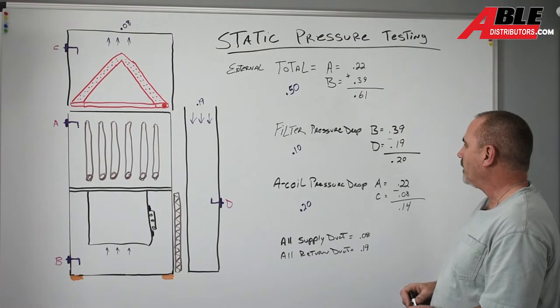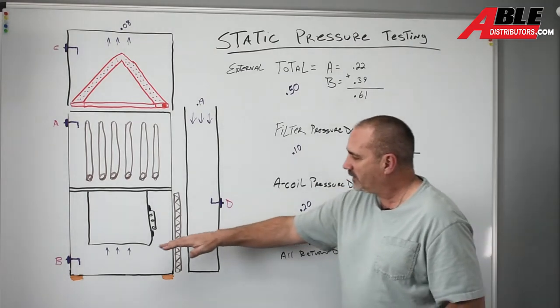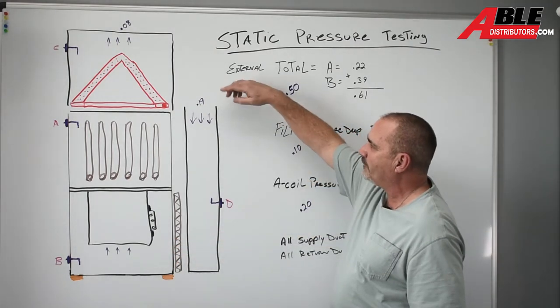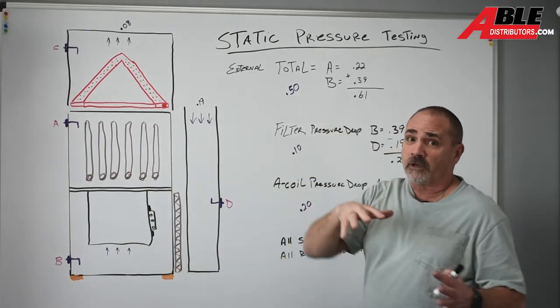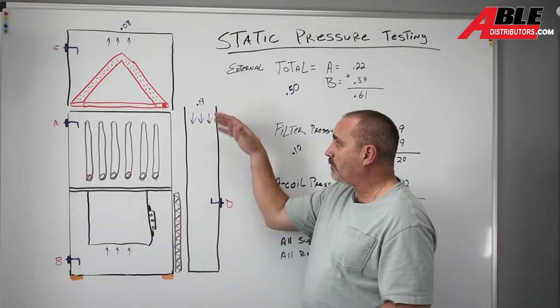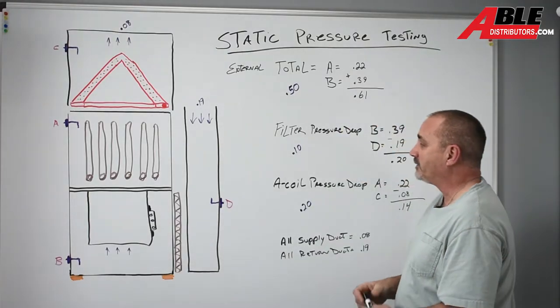So we know something's going on there, but that tells us another thing. It tells us that all the duct work past that, the static is 0.19, and that's also kind of high. So we're seeing more problems on the return side in this scenario than on the supply side. But let's double check it.